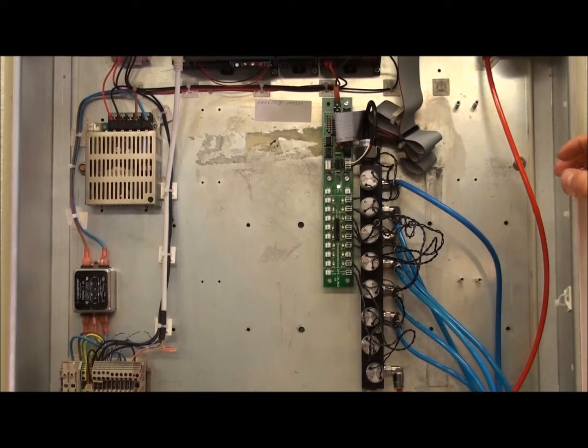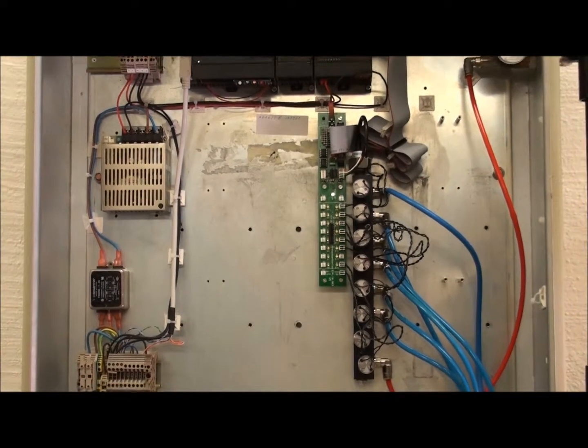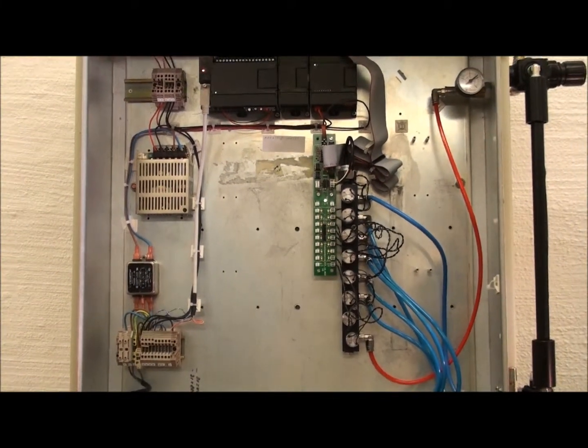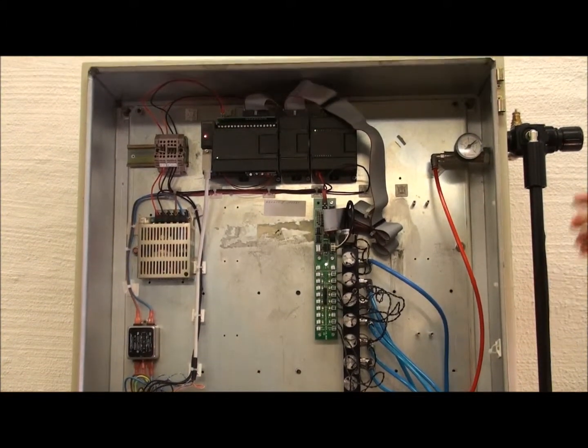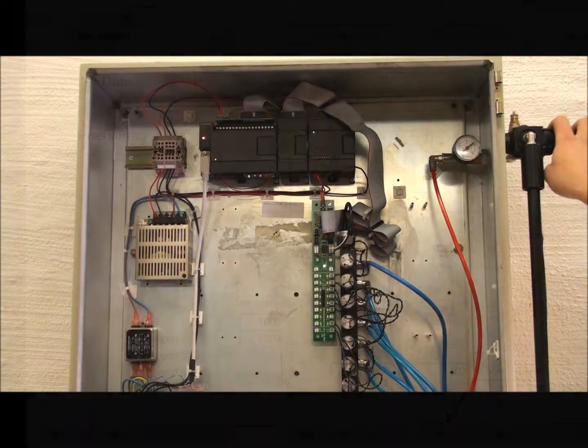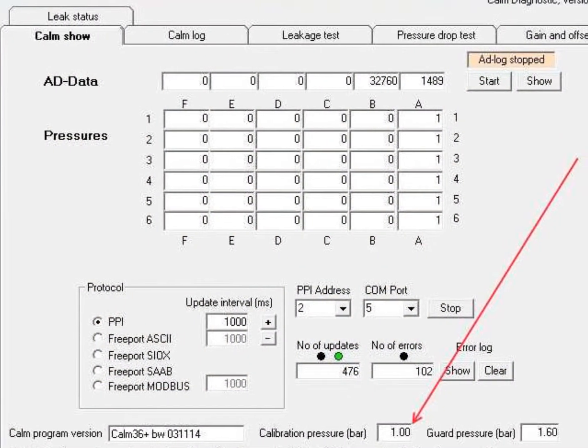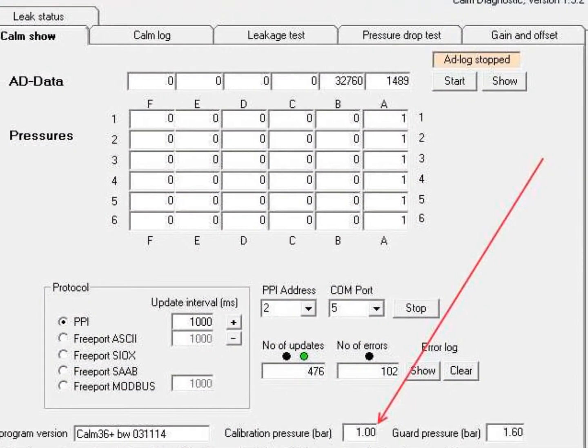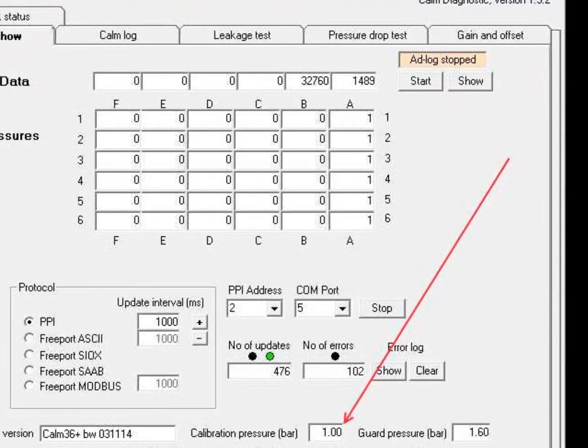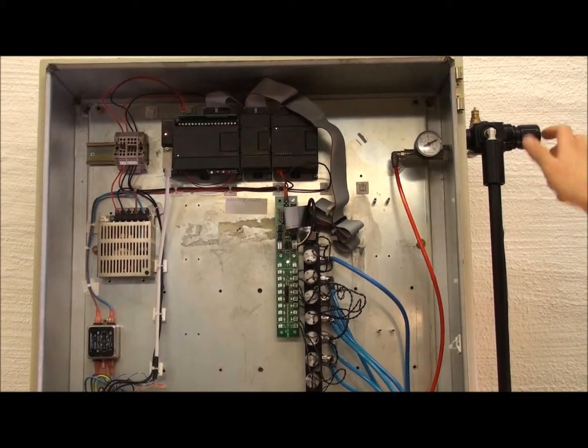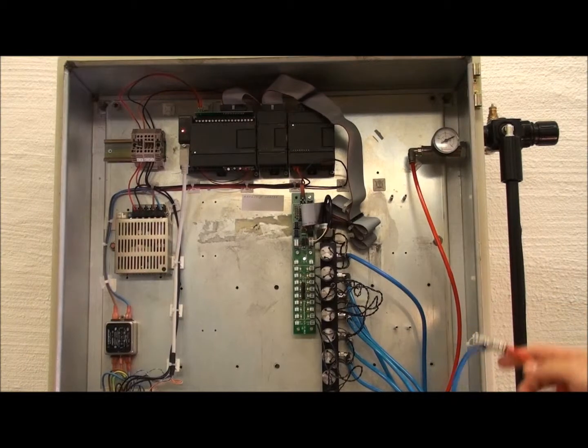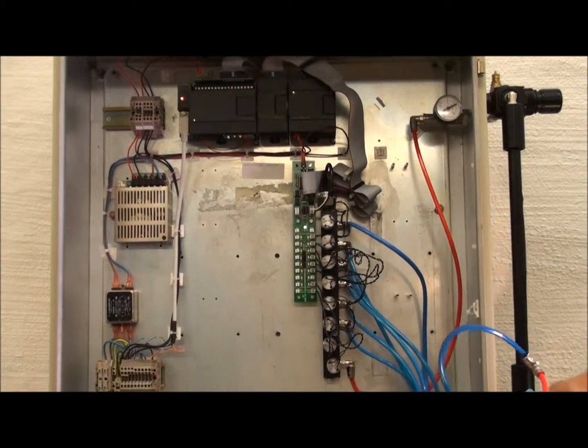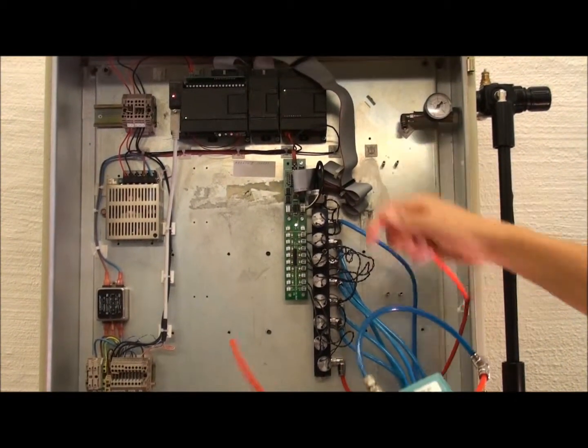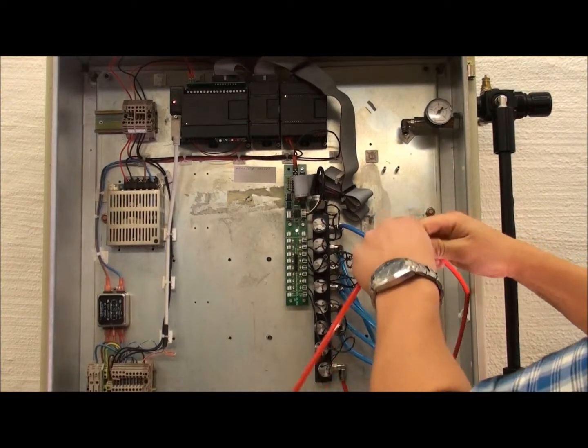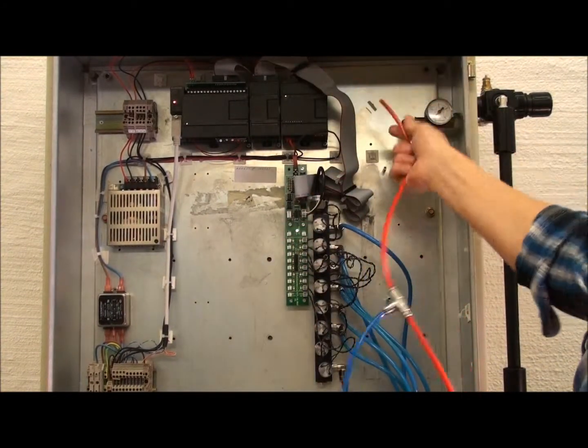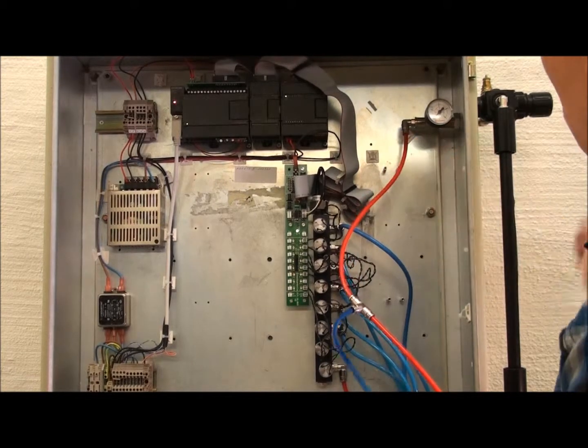So the first thing to do is to check in the CALM diag what is the calibration pressure. In this situation, in this occasion, is 1 bar, as you can see in the picture there. Then we go down with the DPI. So we turn off the supply. We connect us in between the line, so we can check that it's actually 1 bar, and exactly 1 bar.